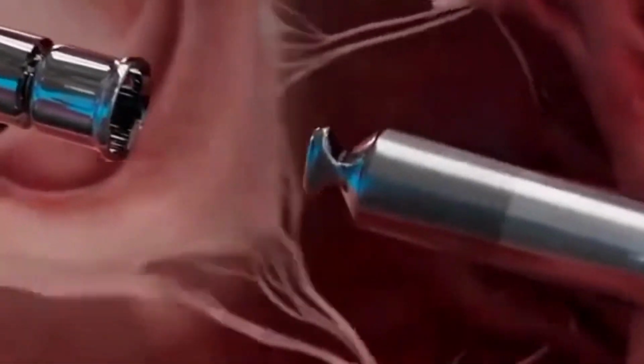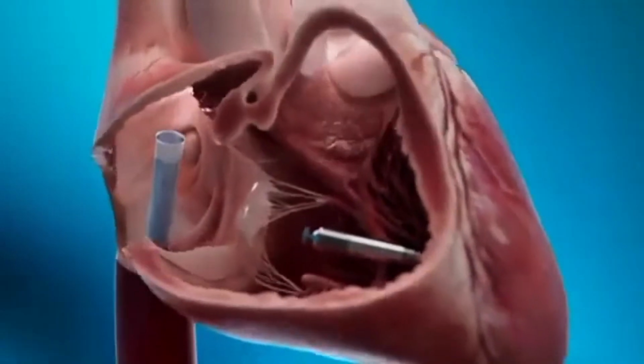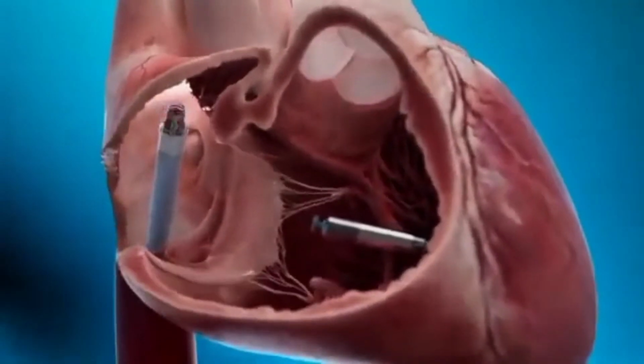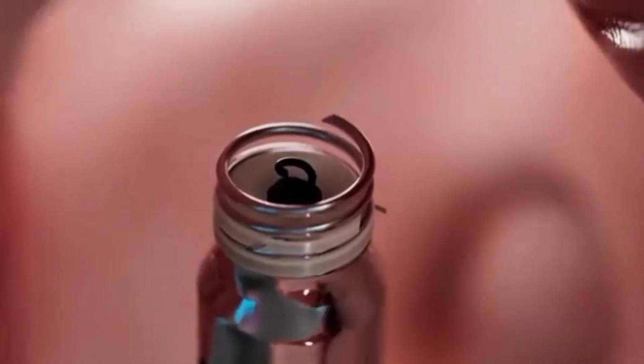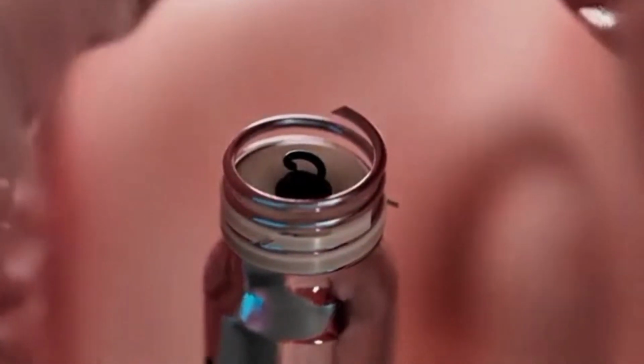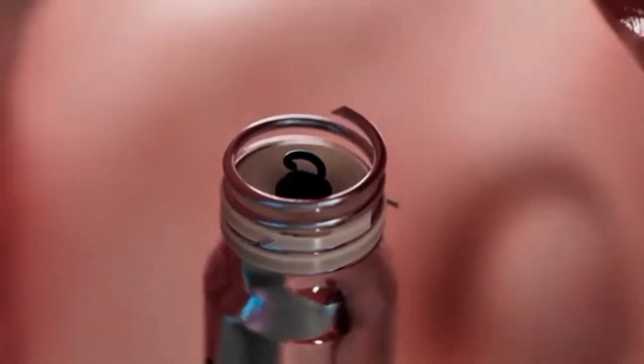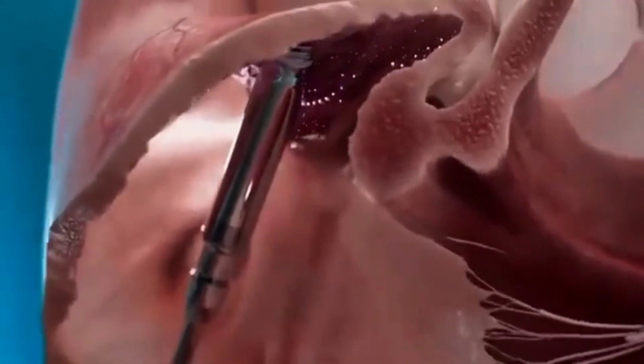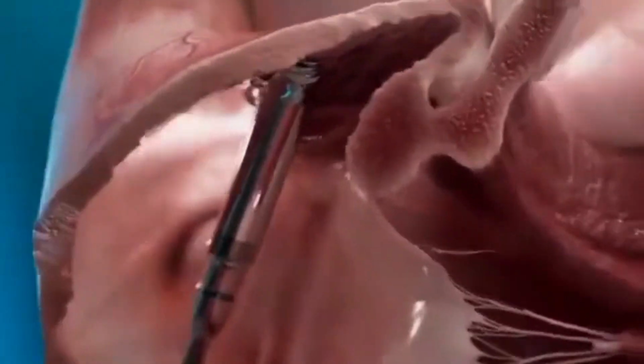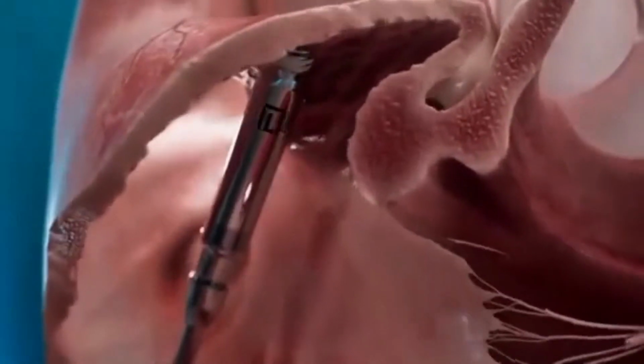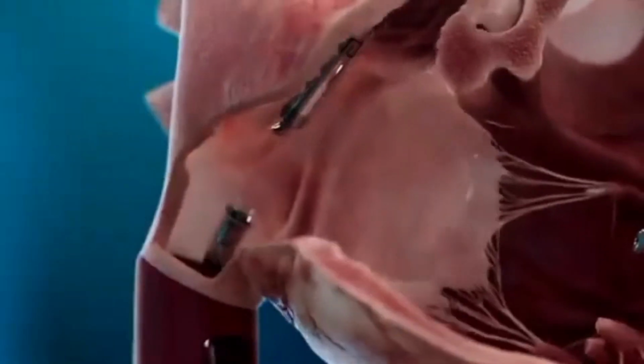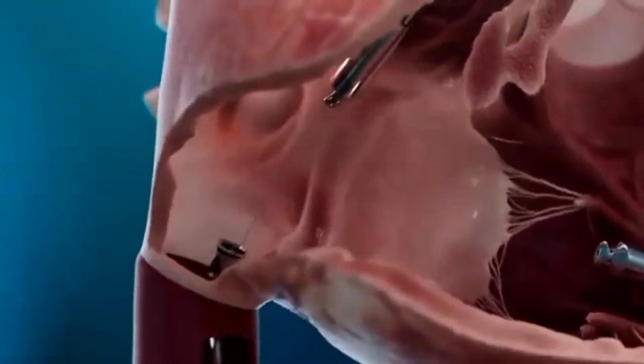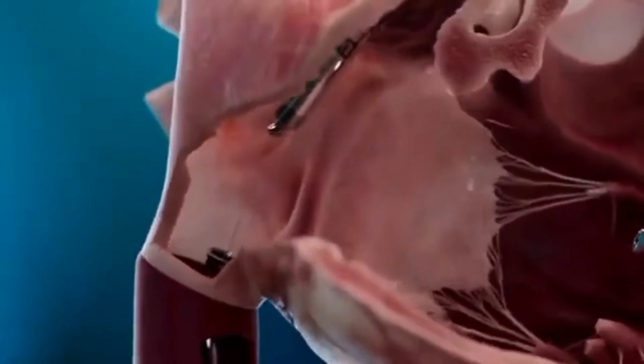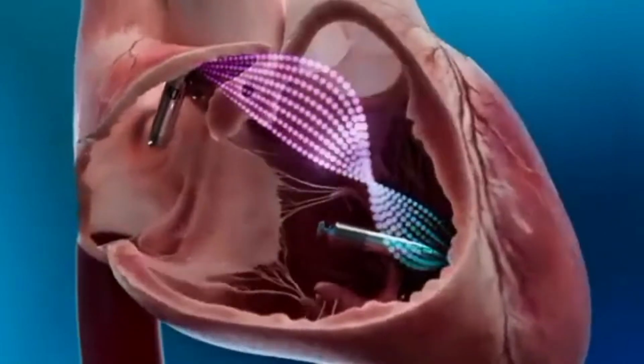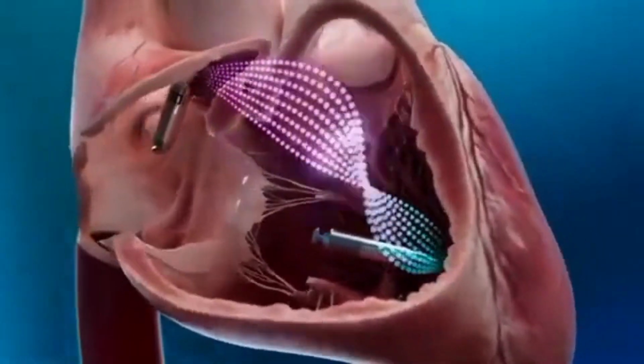The catheter is removed, and a new delivery catheter and device are inserted to support the implant of the atrial device. The atrial device is smaller and has a double helix designed to better accommodate the specific characteristics of the right atrium. The atrial device is advanced to the right atrium, where mapping prior to fixation is performed again, ensuring the optimal location. Once the device is fixated, the catheter is placed into tether mode for final testing. It is then released. The two devices undergo implant-to-implant pairing, and implantation is complete.